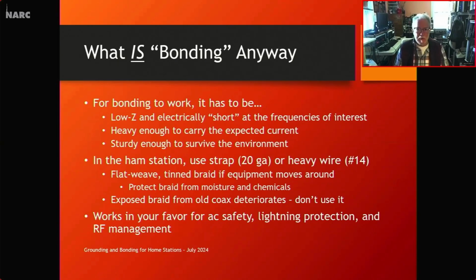So whatever your intent for the bonding connection, you have to know what kind of maximum current it's going to carry. It also has to be sturdy enough to survive what happens to it in the environment. And that's why when you look at your building codes and you talk about outside earthing conductors and whatnot, they're much larger than you might expect. Over here in the States, we would get into number 6, number 8, number 2, rather large conductors as big as my little finger. And part of that is mechanical, because the buried conductors outside are going to be subjected to being driven over. You're going to hit them with the shovel when you're digging in your garden.